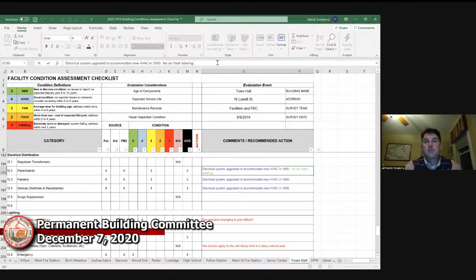Realistically, arc flash would be part of your coordination study, and all of the arc flash warning labels would be derived from the available incident energy developed during that study. So unless you're going to go back and generate a coordination study for every building, you're never going to get arc flash labels that are actually accurate for the panels, the loads, the available fault current, etc.